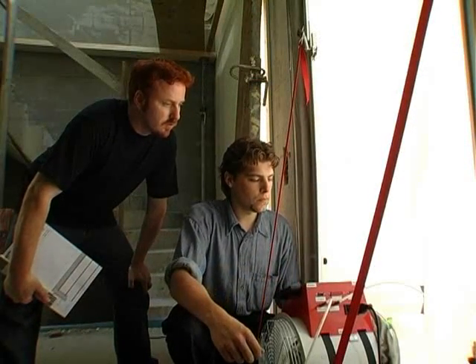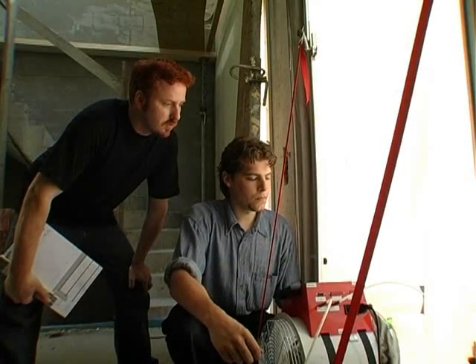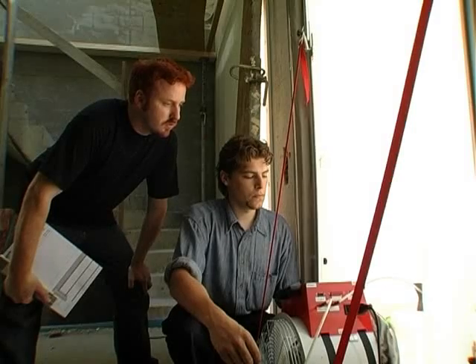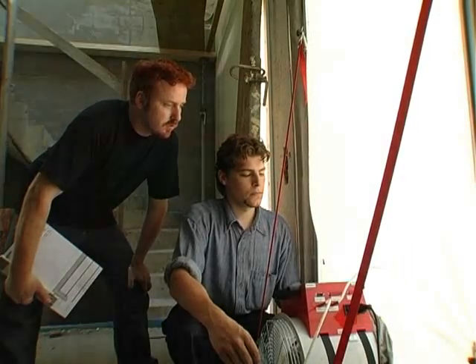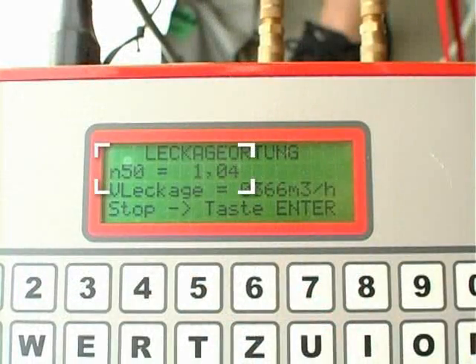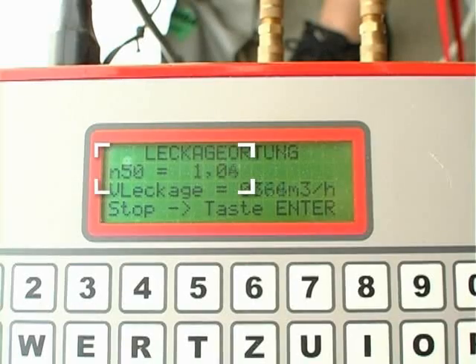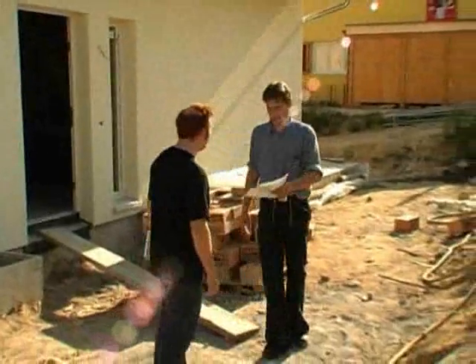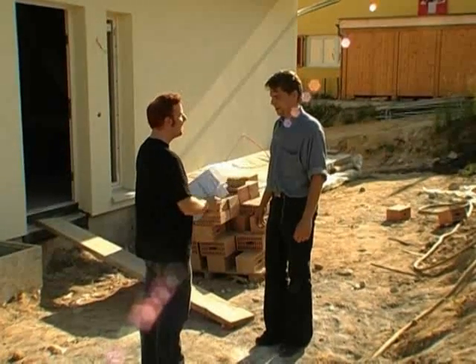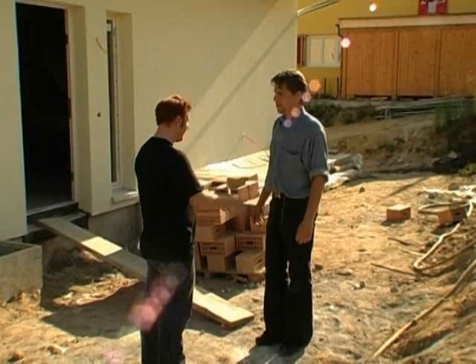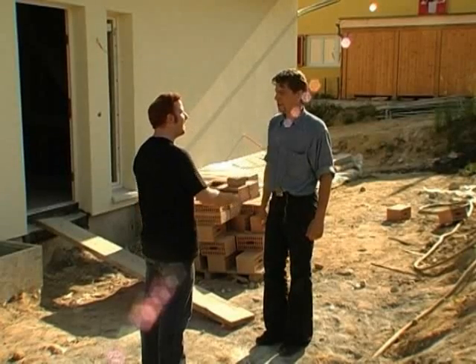Finally, contractor Connor repeats the blower door measurement to assess what improvement has been achieved by the corrections. The air change rate is now well below the required maximum of 1.5, resulting in satisfaction all round at the job site. Contractor Connor hands the architect a test record for the measurement that was performed.